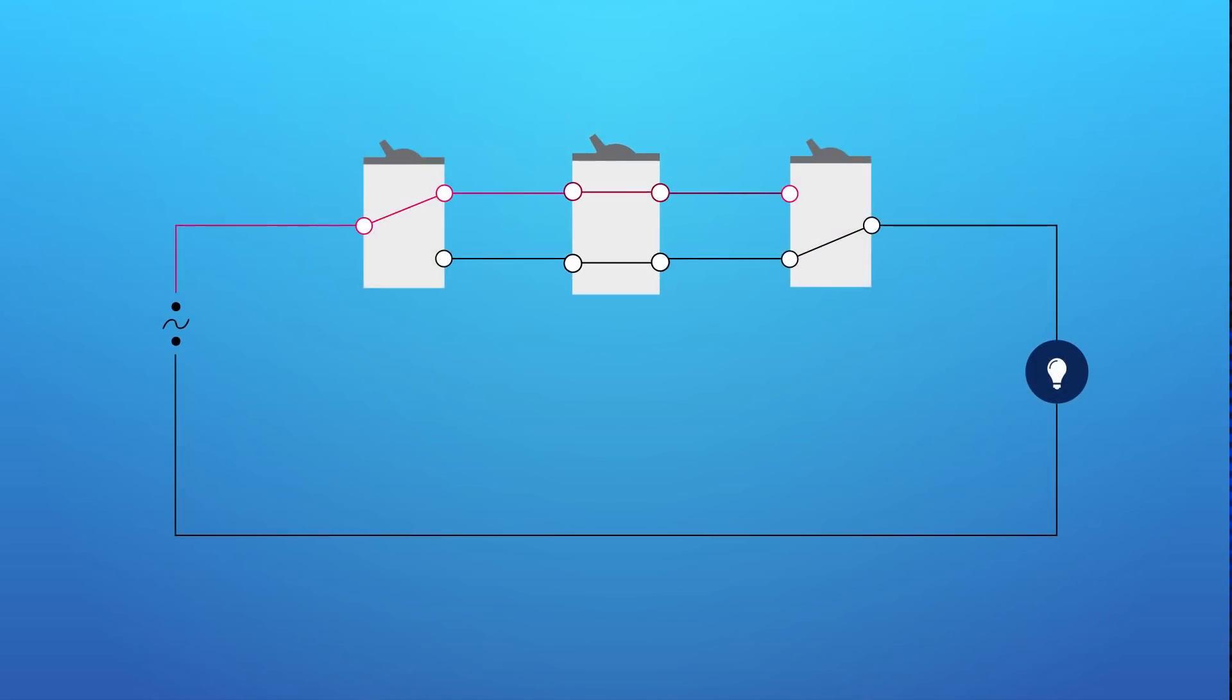This switch is installed between the other two and toggles the active traveller. This means that any switch can turn the light on or off. With this concept you can add an endless amount of four-way switches into the circuit as long as you have three-way switches at each end.